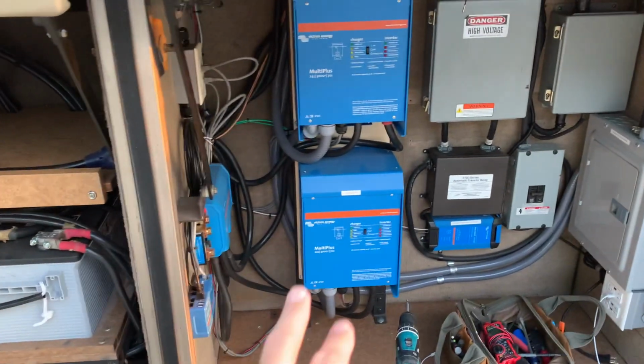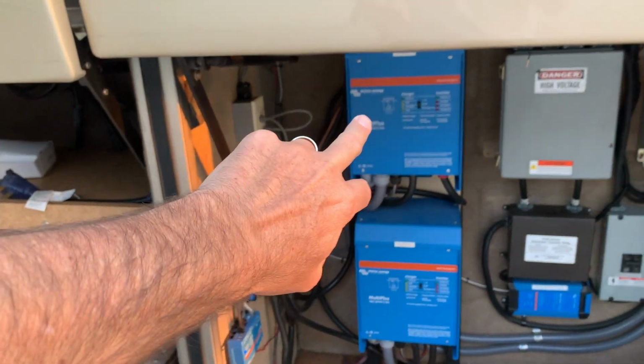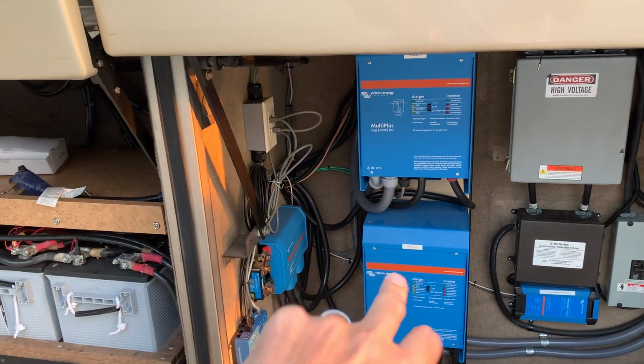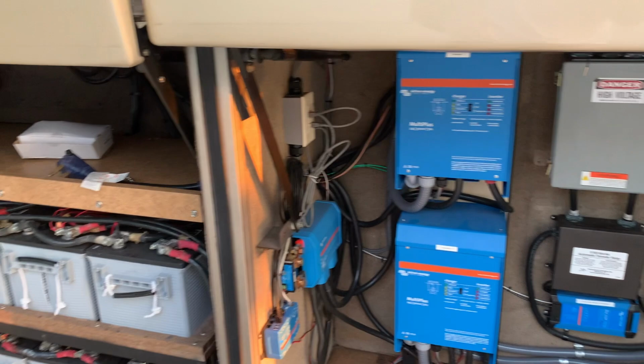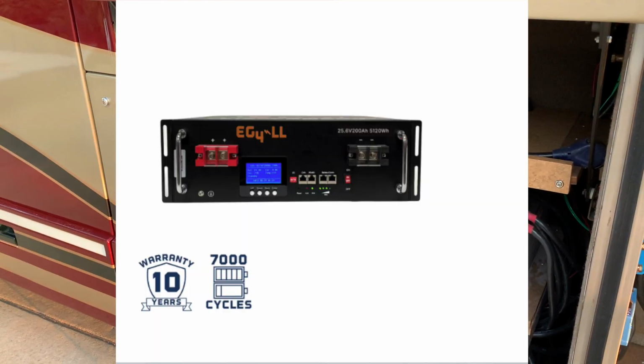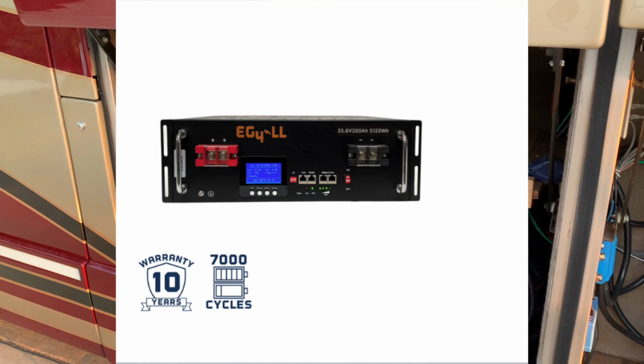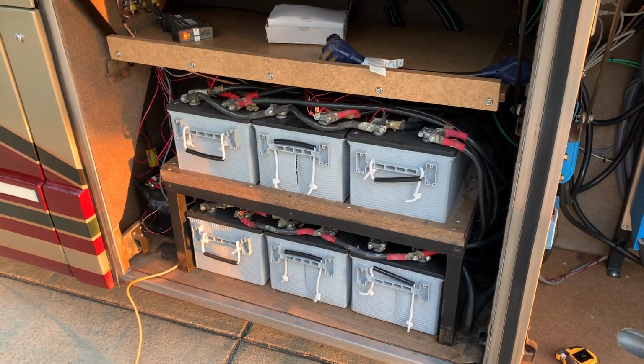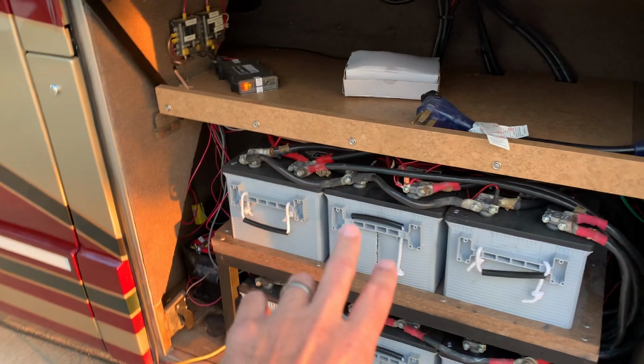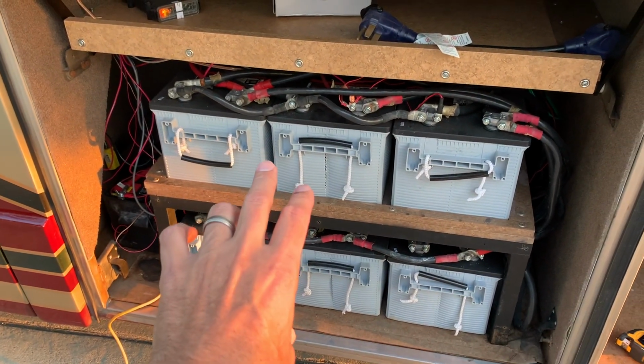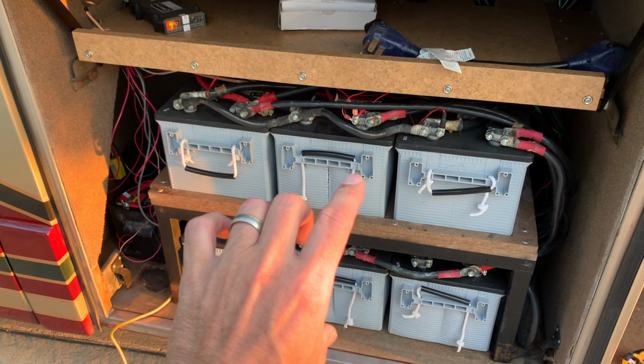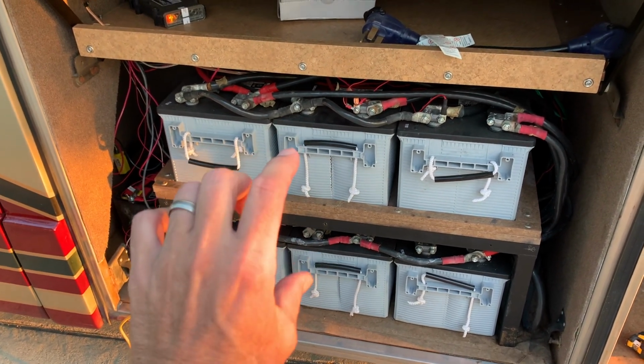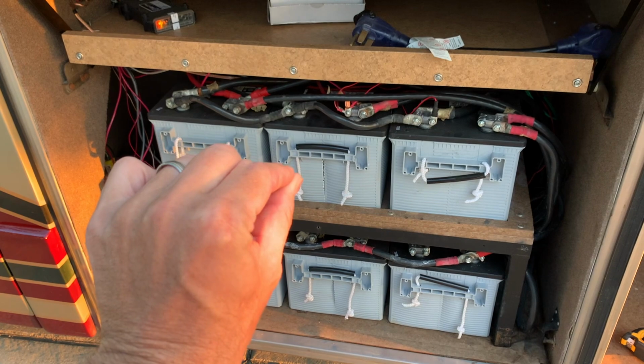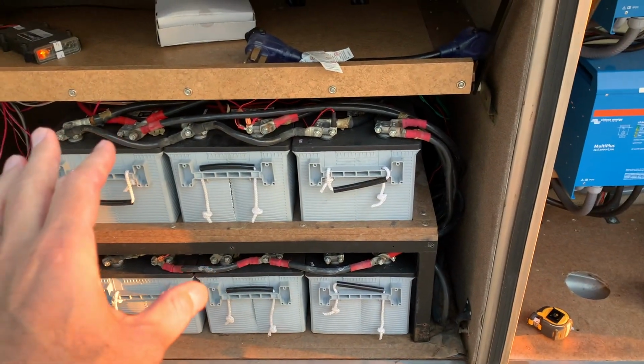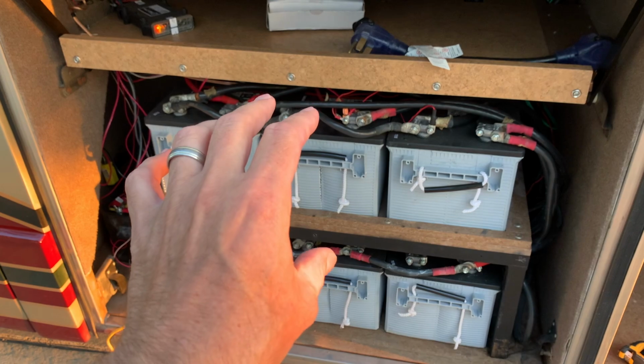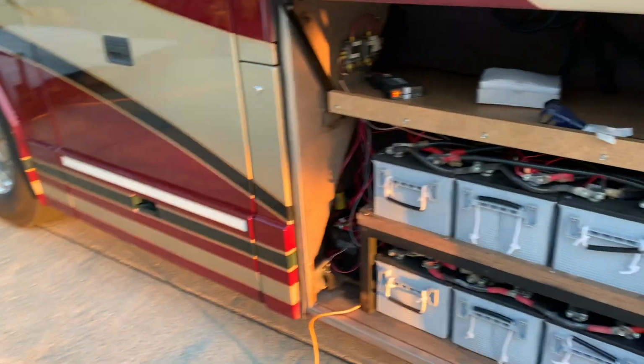The one problem I'm going to have is I've got a 3000 watt and a 3000 watt inverter, and they're going to pull from a 5000 watt, 100 amp battery. But I'm gonna make this 24 volt instead of two 12s, because if the BMS in the 12 volt batteries that are making the 24 goes out, then I've got a 12 volt battery in between a 24 volt system, and that's bad.